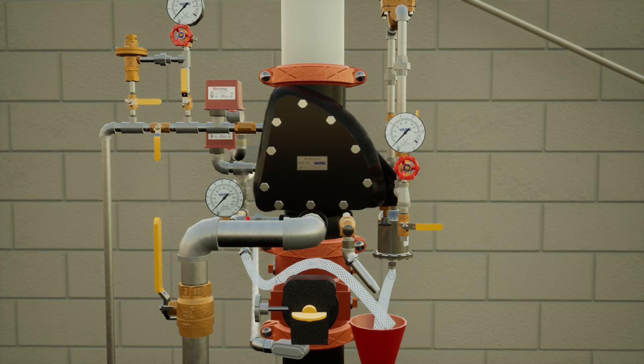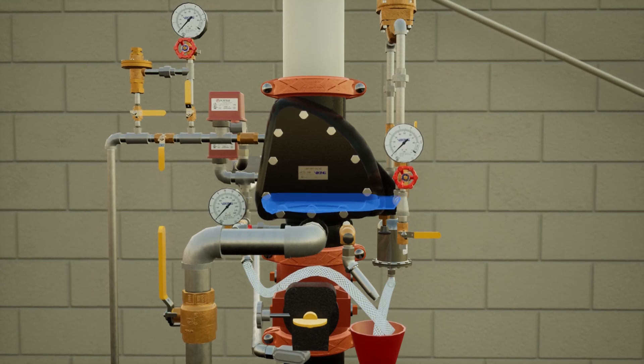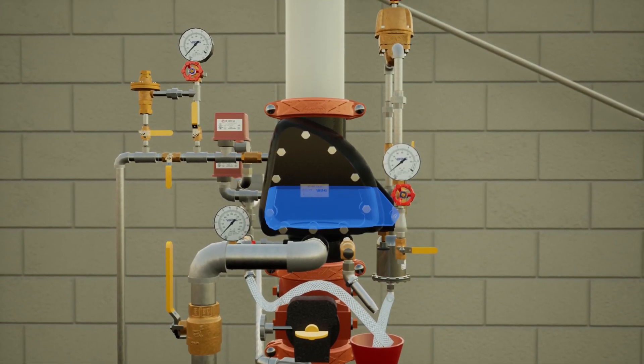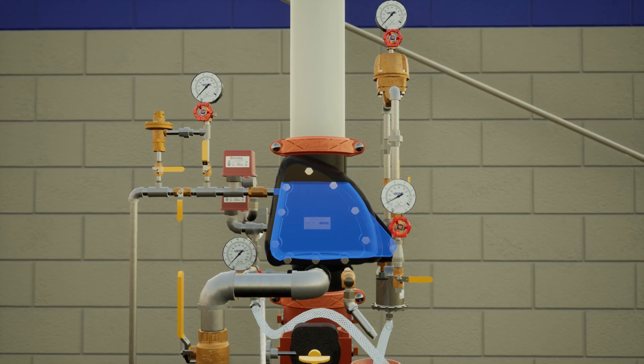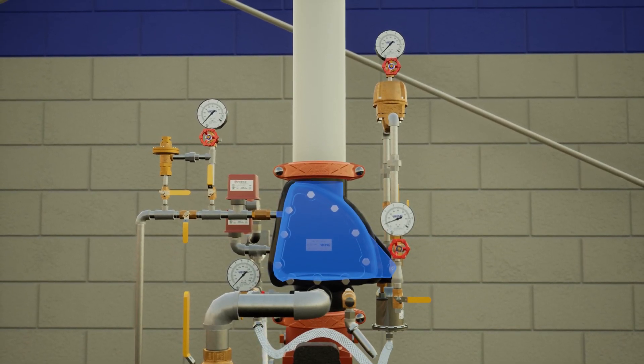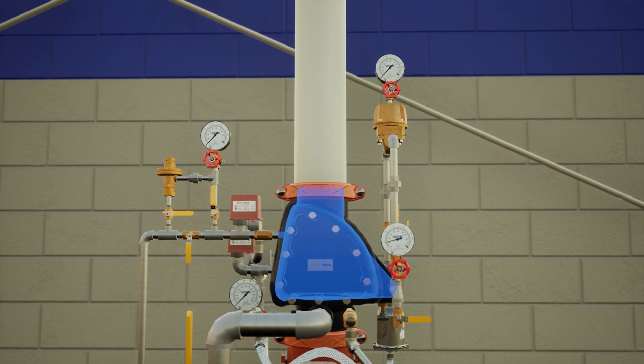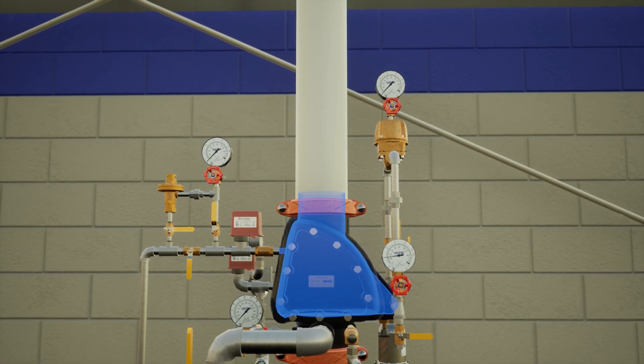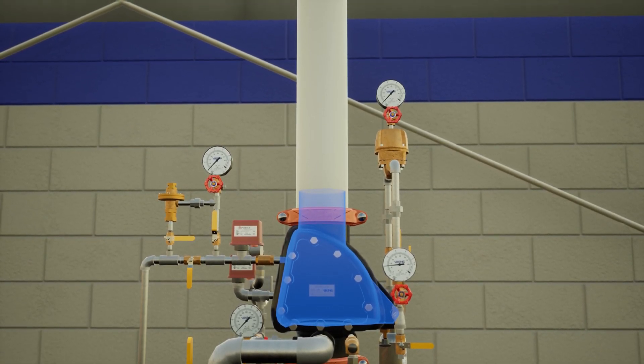If the system was not fully drained or if excessive condensation forms in the pipes, a water column may form over the clapper. Since the VXR operates on a 6 to 1 pressure differential, even a moderate amount of water resting on the clapper can impede system operation.